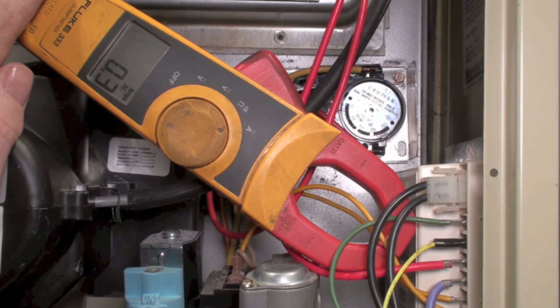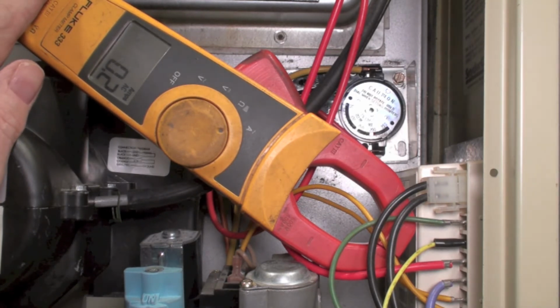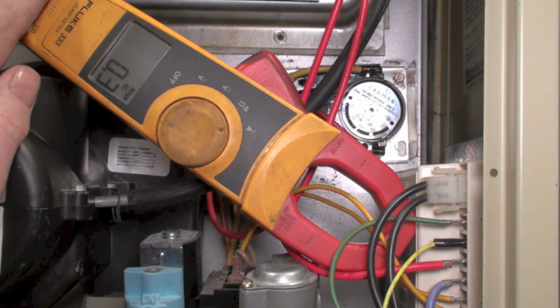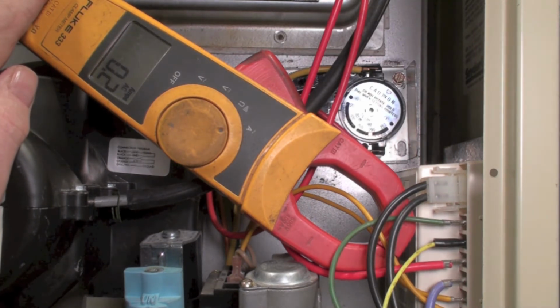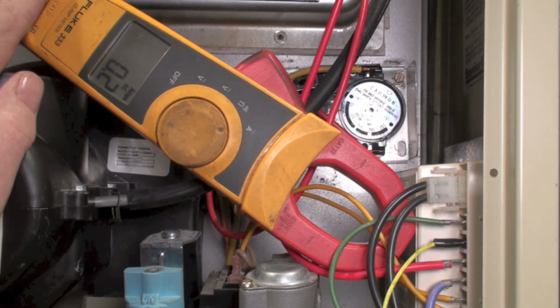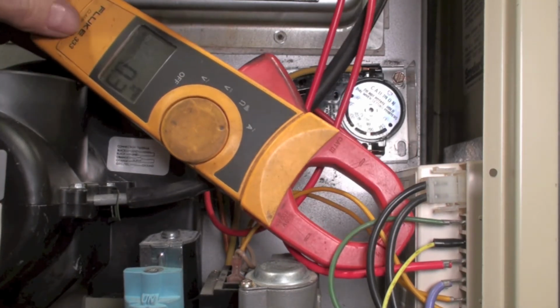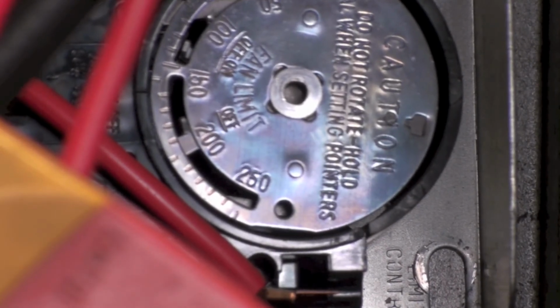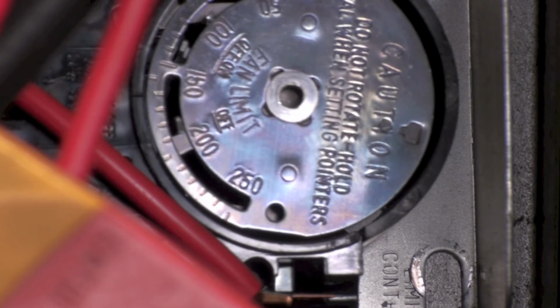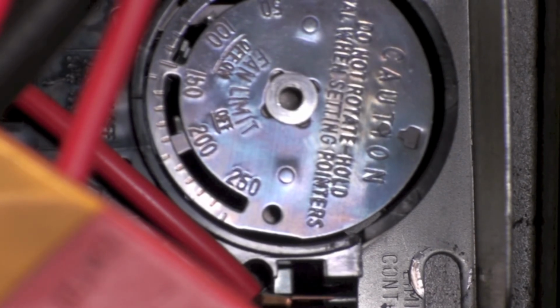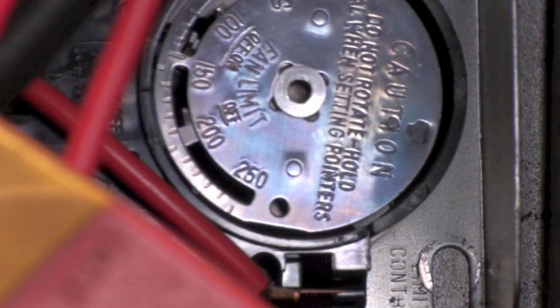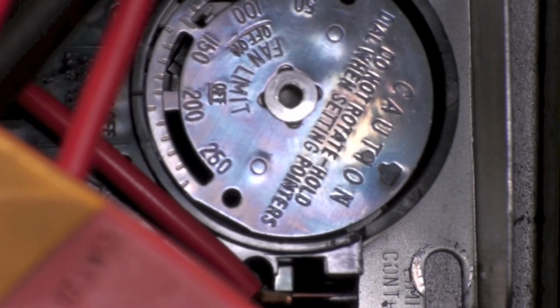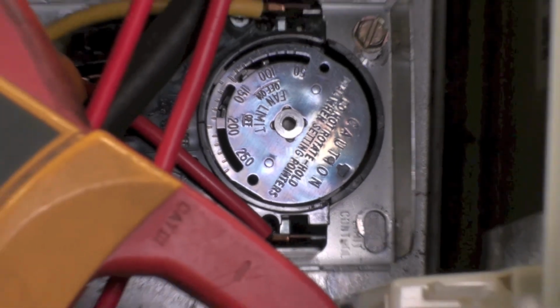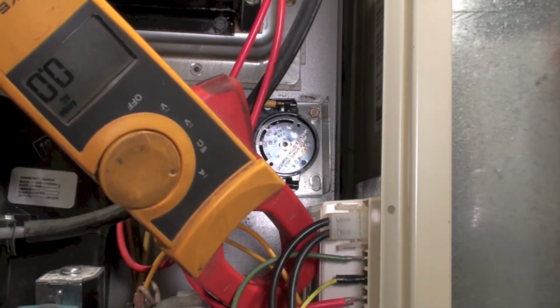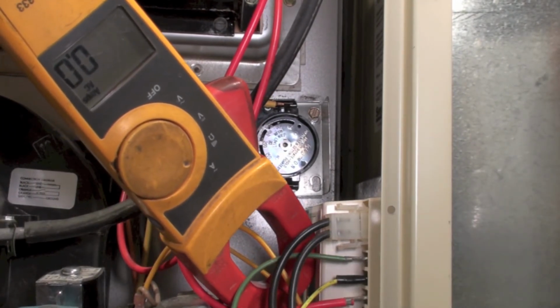I'm not going to go through all the service checks on the fan motor. I'll give you a reference to a video where I did all that in the same type of furnace. But all I'm going to do now is I'm going to watch that limit switch go up, and we'll see if it shuts off the burner. It looks like we kicked off. Back out here, you can see my ammeter says 0, so it has shut off.